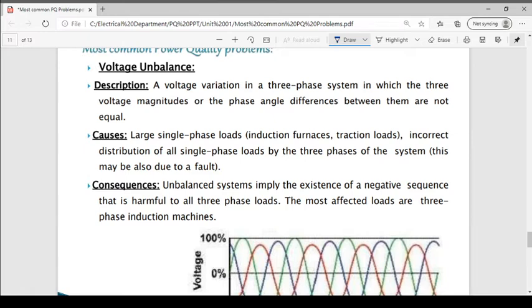So what are the causes? The causes behind the voltage unbalance are large single phase loads like traction loads and induction furnaces, and incorrect distribution of all the single phase loads across the three phases of the system. This may also be due to faults, like symmetrical and unsymmetrical faults, which are major causes behind the voltage unbalance.